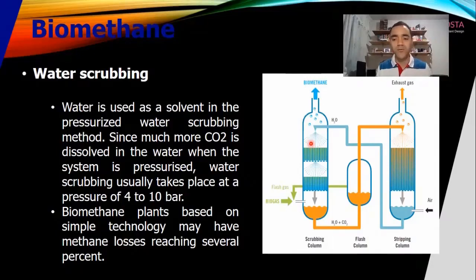And in terms of operations, we must monitor the pH of this water, and from time to time we need to do a blowdown, or we have to have a continuous blowdown, because we are not able to remove 100% of the CO2 from the water. And to not saturate it and to not lose the quality of the gas, we need to renew the water.